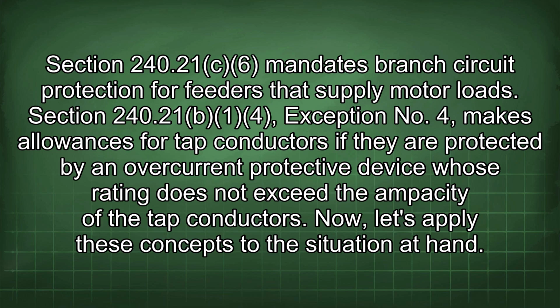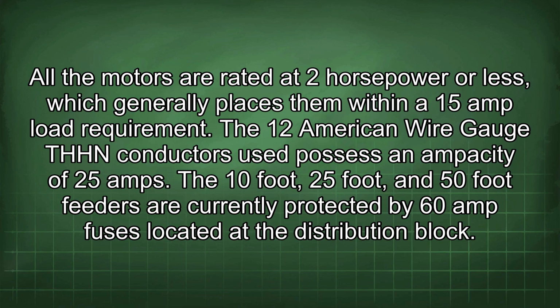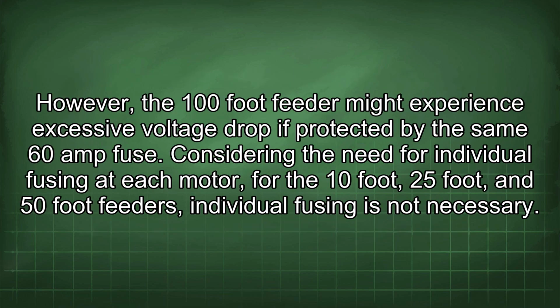Now, let's apply these concepts to the situation at hand. All the motors are rated at 2 horsepower or less, which generally places them within a 15 amp load requirement. The 12 American wire gauge THHN conductors used possess an ampacity of 25 amps. The 10-foot, 25-foot, and 50-foot feeders are currently protected by 60 amp fuses located at the distribution block. However, the 100-foot feeder might experience excessive voltage drop if protected by the same 60 amp fuse.